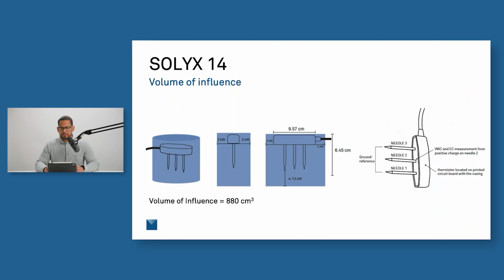Other things we always continue to focus on with these measurements is trying to improve our volume of influence. As we know, soil moisture is a spatially variable parameter. So the bigger volume that we can measure in soil, especially in the field, the better job we're going to do at encompassing some of that variability. Here you see an example of how this probe is measuring on the right. We have our active pin in the middle, and then our two grounding pins on the needle 1 and 3, so the two outer needles. What that does for us is it creates a sensor with a pretty large volume of influence. This sensor has about an 880 cubic centimeter volume of influence, which is great for making sure that we maintain a good volume of influence with this measurement.